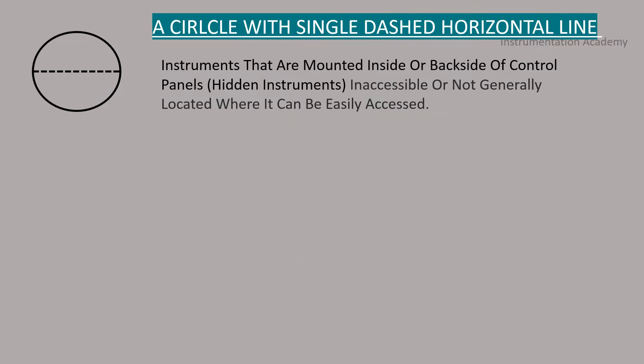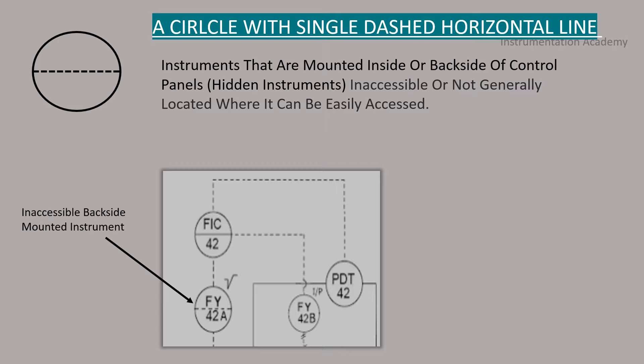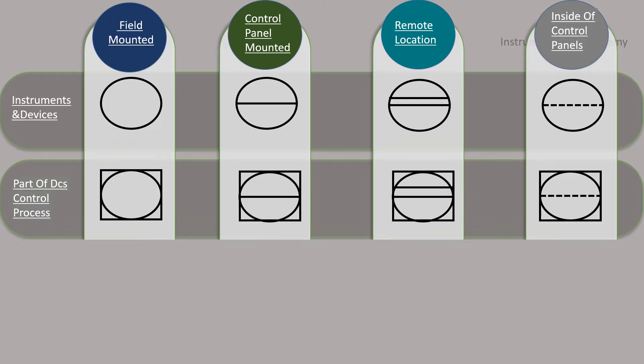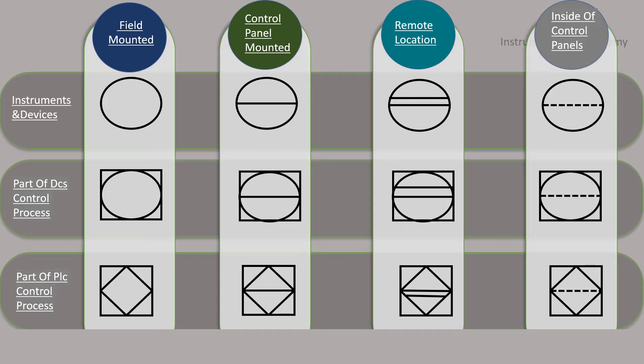A circle with single dashed horizontal line. This represents the instruments that are mounted inside or back side of the control panel which are generally inaccessible. These are the symbols associated with instruments. If these symbols are enclosed within a square, it means that they are a part of DCS control process. If the shape of the symbols are diamond enclosed within a square, it means that they are a part of PLC control process.